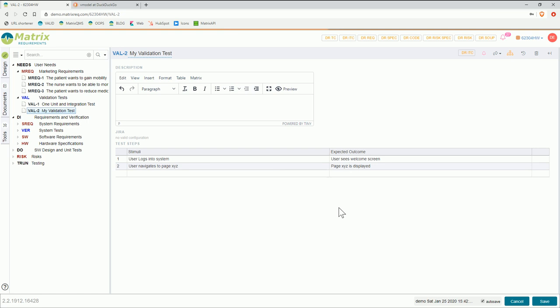Here, what you need to do in order to write good tests is basically take validation tests from the perspective of a persona who needs to run the test. The test should be written in such a way that, for example, if you have a patient doing it, it should be from the view of a patient, not of an experienced engineer. You should describe what the patient would do because it's a validation test.